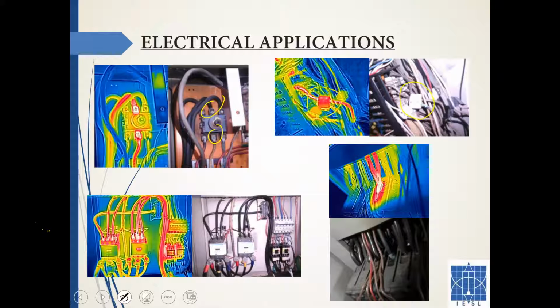And yeah, this is an interesting image right here. You can see from the side, these are the two contactors. You can see from the side that these contactors, internally they have many components. They have their electromagnetic coils, they have their contacts, right? So based on the thermal signature, your thermographer should be able to identify what the problem is. Is it the coil or the bad contacts? Accordingly, he must recommend suitable action.